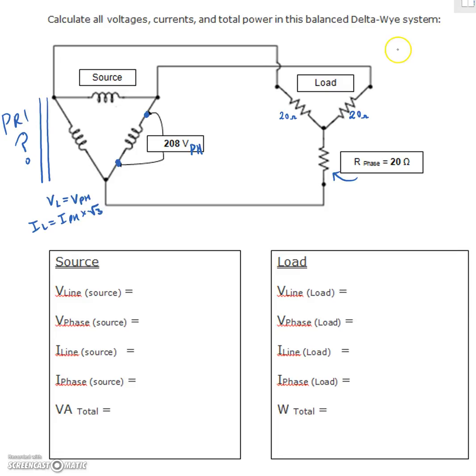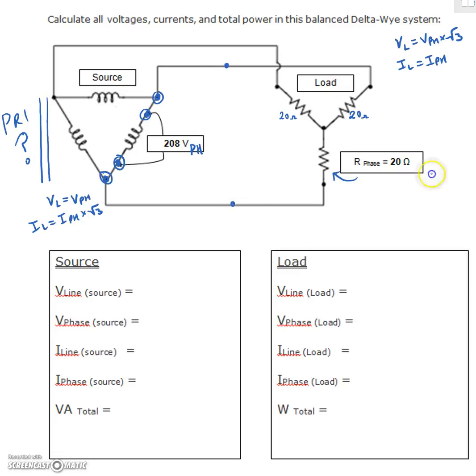For the Y connection, V_line equals V_phase times root 3, and the phase current and line current are identical. Looking at the delta source, V_line equals V_phase, so the voltage on the outside of the circuit equals the voltage on the inside — meaning the line voltage is 208 volts.